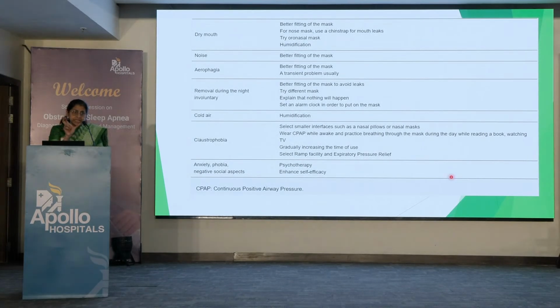and then gradually start using it at night. There are also facilities in the machine itself where you can select the ramp facility so that the pressure slowly increases and the patient does not have a high pressure immediately. There is also an expiratory pressure relief valve, so we can use that so that very high pressures don't build up. It's also very important to do a titration study so that we know what pressures are required. Many times the mistake is that the patient is directly put on CPAP, and the CPAP has a range from 4 to 20, so there are fluctuations, and because of these high fluctuations, sometimes it wakes up the patient.